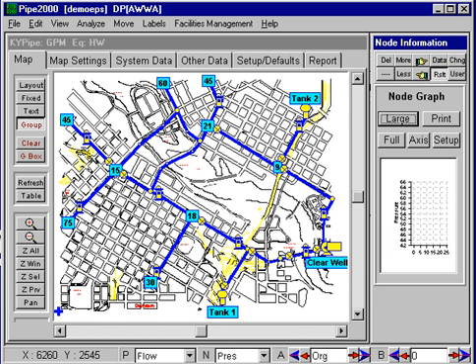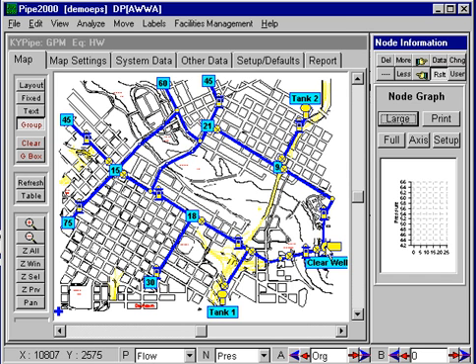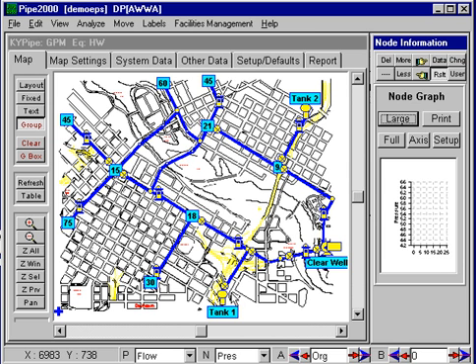So we put in the EPS data and some demand patterns, which is normal in EPS. Another feature here is that this pump will be controlled by the water level in one of these tanks — in this case, Tank 1. When the water level goes below a certain value, the pump will come on, and when it goes above a certain value, it will go off.